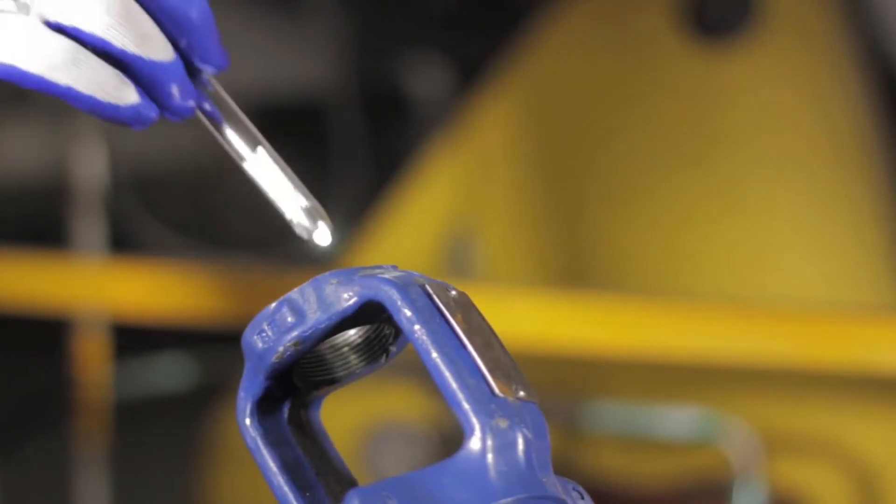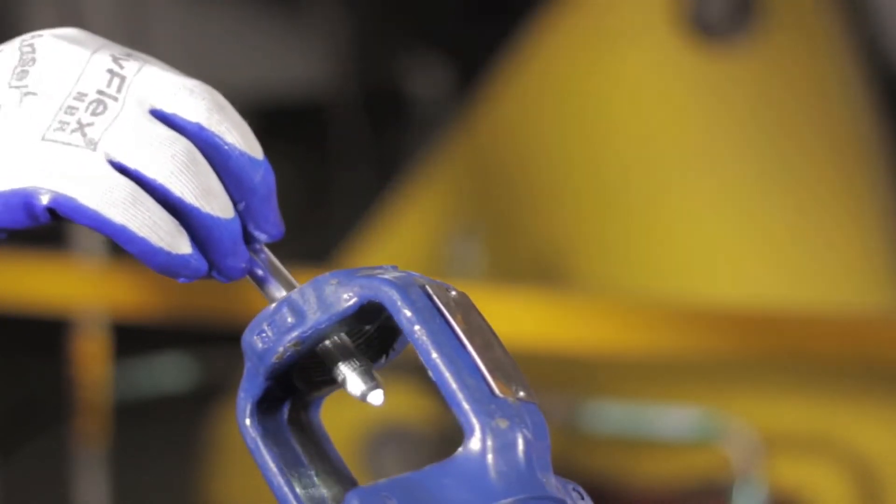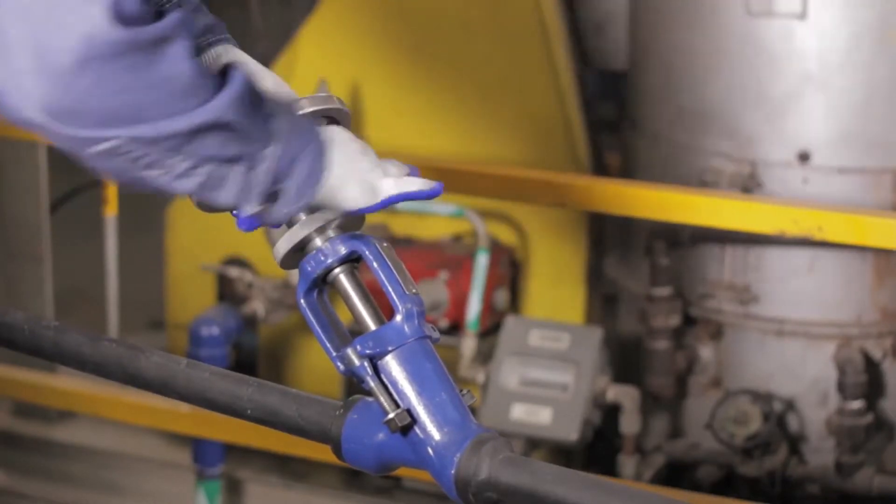You can do this fairly easily on small valves by using a flashlight. You should see a shiny surface completely free of blemishes. This indicates that the seat has been fully and evenly restored to its original factory condition.